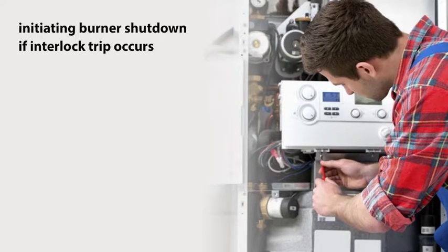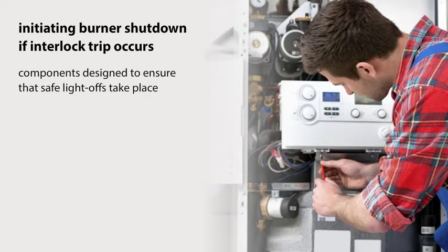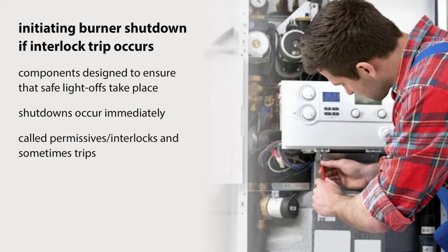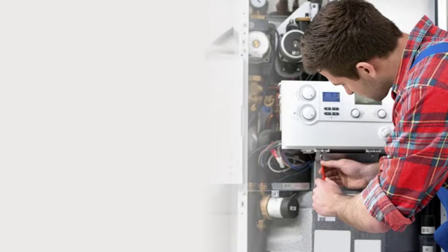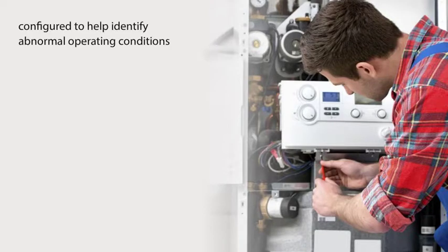Initiating burner shutdown if an interlock trip occurs. Fuel trains also have a number of components designed to ensure that safe light-offs take place and that shutdowns occur immediately if anything goes wrong during operation of the equipment. These components are called permissives or interlocks and sometimes trips. These are a series of devices such as switches or transmitters that are configured to help identify abnormal operating conditions, such as a loss of gas or air pressure or water level problems in a boiler.